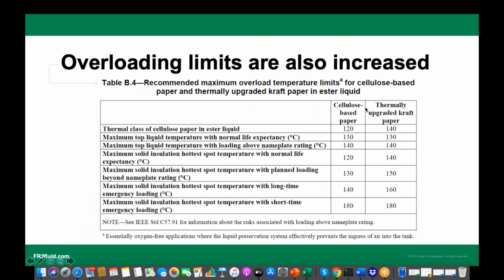So because of this, what you typically get is, let's say, a 400 kVA transformer doing a 630 kVA job, so today your load is less. That means you get not only 630 kVA additional capacity, but also extra overloading capabilities, because your 400 kVA transformer sometimes can be overloaded as high as 700 kVA. And today, because of the lower efficiency and all that, you get that extra power in the transformer, and it can be overloaded, and you get increased capability in the transformer. If somebody has a question on that, we can discuss in detail. In the pressure of time, let's move to the next slide.